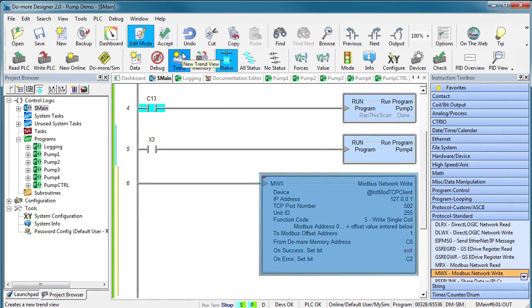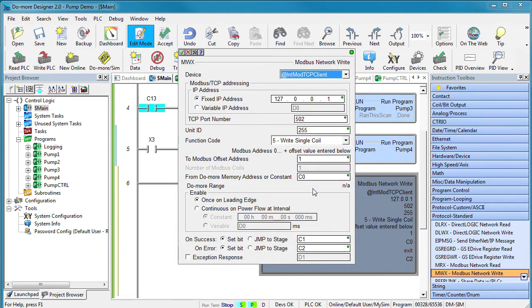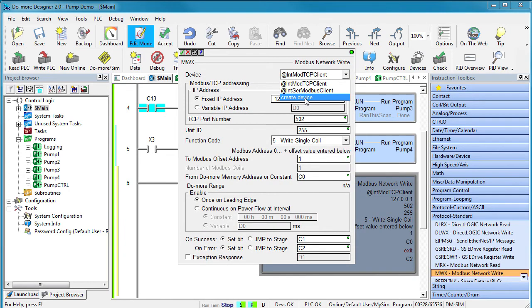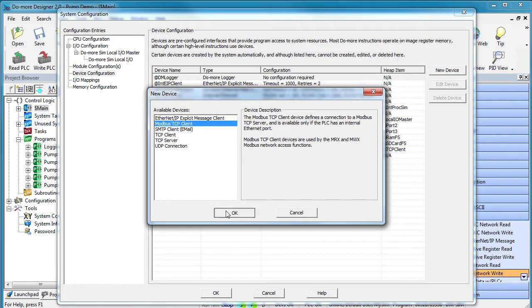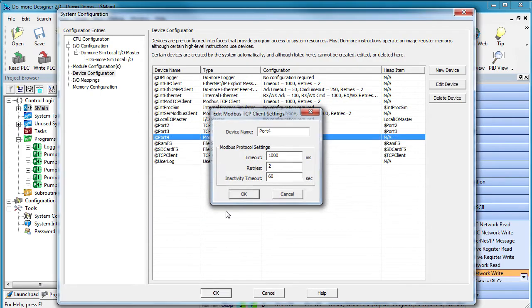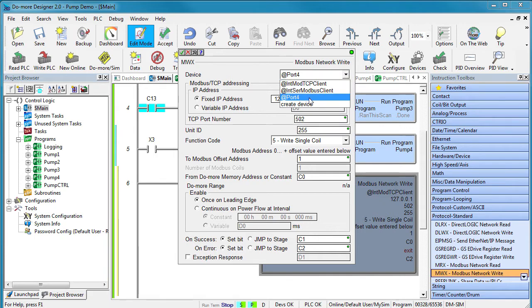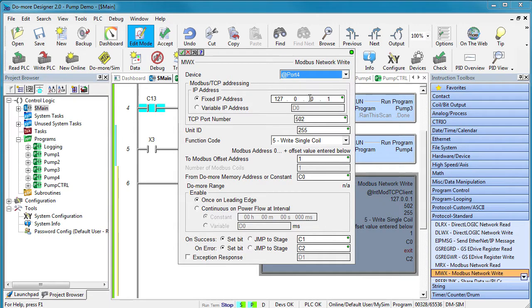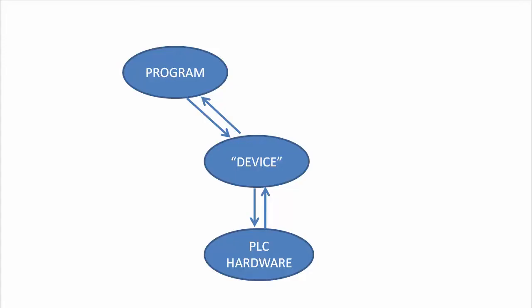What if I wanted to send data out an additional serial port module and I haven't set up the device yet? Well, look at this. You can set up the new serial port device which DoMore created for you automatically right from within the instruction. Now just use that device and away you go. We just set up three different ways to get data out of the DoMore and all we did was swap out devices.